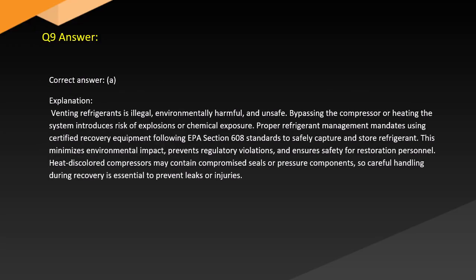Answer. Correct answer: A. Explanation. Venting refrigerants is illegal, environmentally harmful, and unsafe. Bypassing the compressor or heating the system introduces risk of explosions or chemical exposure. Proper refrigerant management mandates using certified recovery equipment following EPA Section 608 standards to safely capture and store refrigerant. This minimizes environmental impact, prevents regulatory violations, and protects safety for restoration personnel. Heat-discolored compressors may contain compromised seals or pressure components, so careful handling during recovery is essential to prevent leaks or injuries.